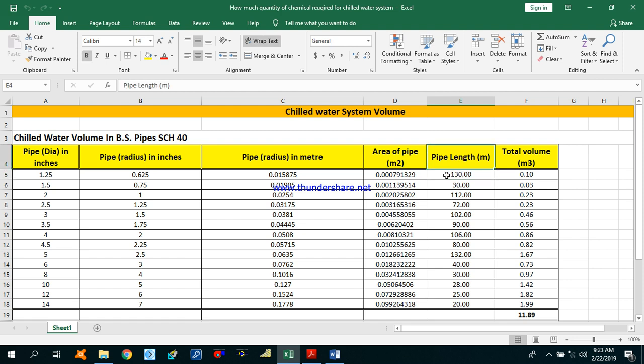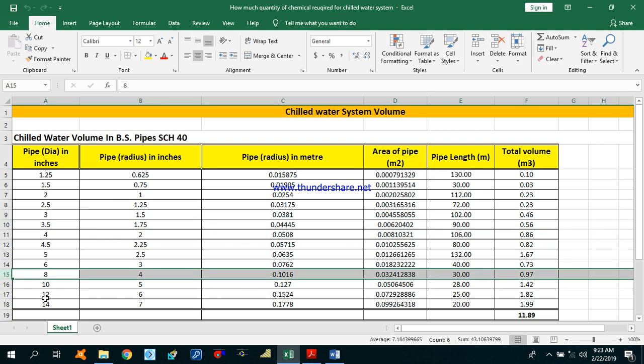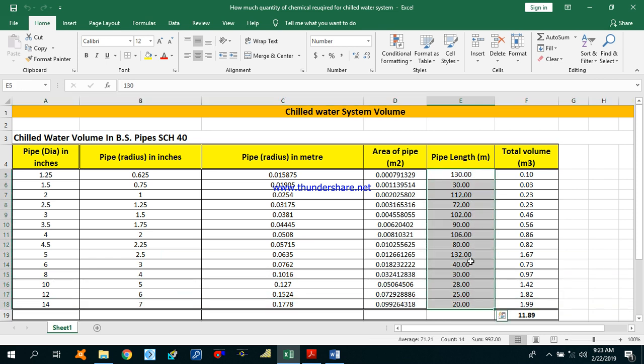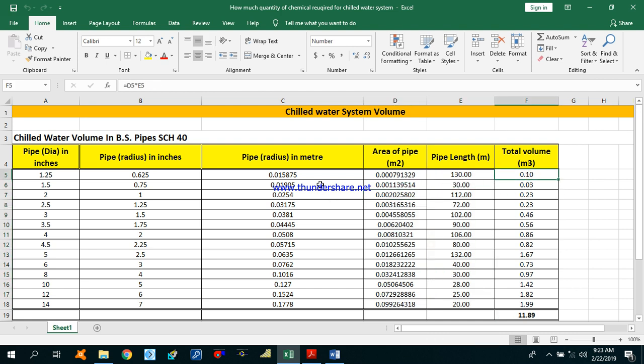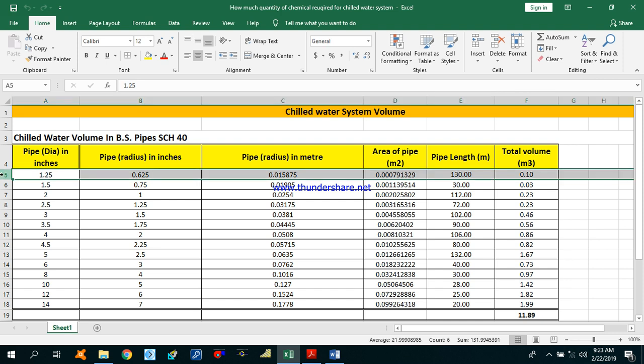Let's move to the next column, that is pipe length. You can get this pipe length from your drawings. For 1.25 inches diameter we have used 130 meters in our project, 3.5 inches we have used 90 meters, 8 inches we have used 30 meters, and 14 inches we have used 20 meters. All the lengths are given here. Now we have to calculate the volume for each pipe — the area of the pipe multiplied by the length gives the total volume for each diameter pipe used in the project.